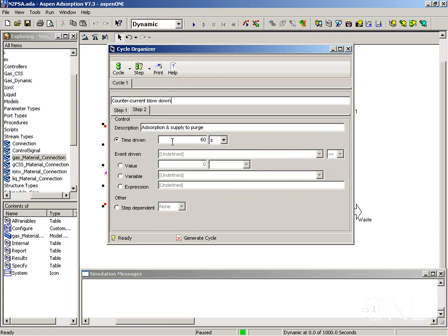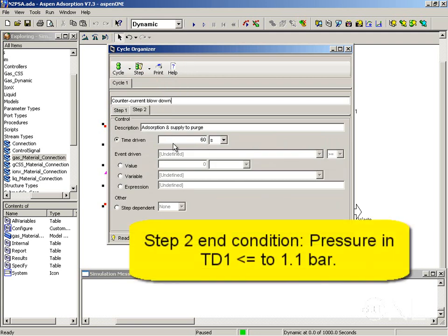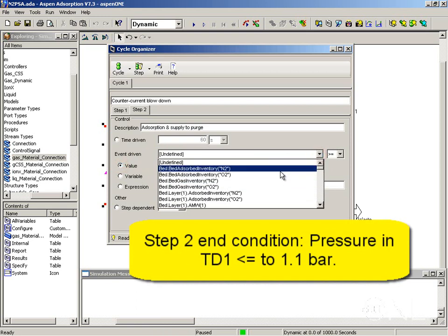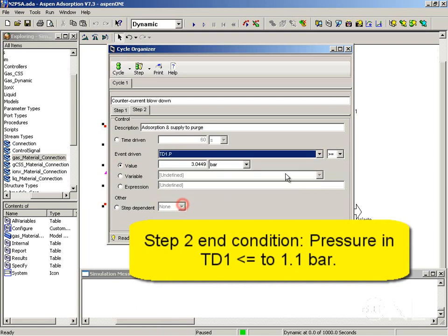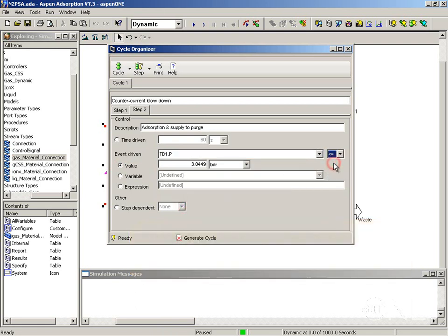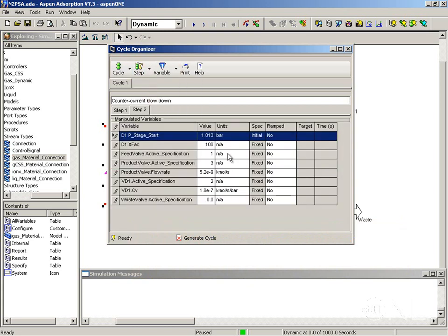So let's look at the control. In this case this step is event driven. And what we want to do is terminate the step when the pressure in the bottom tank void TD1 is less or equal to 1.1 bar. So I want an event driven step and I want to find TD1 pressure and I want it to be less or equal to 1.1 bar.